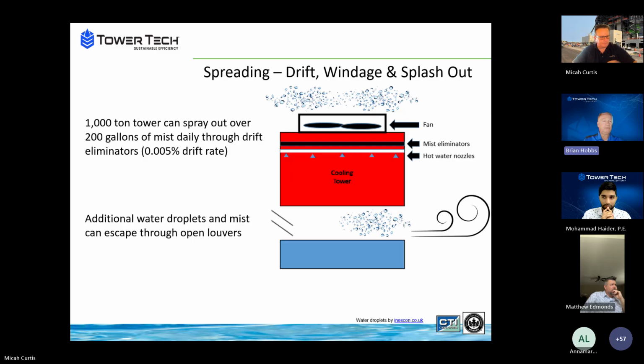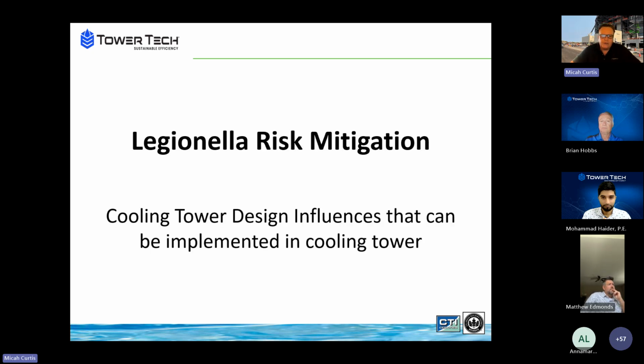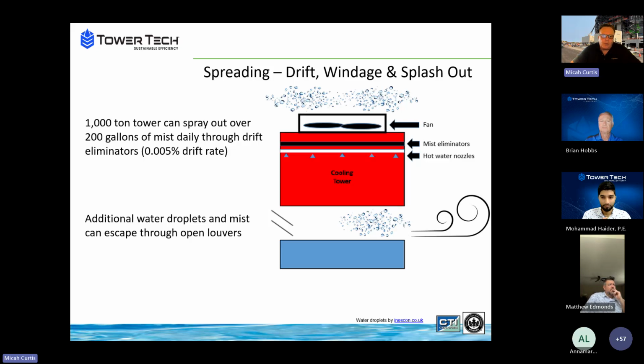Okay, so on a nominal 1,000-ton tower, 3,000 gallons a minute, over the course of a day, you're going to lose 200 to 216 gallons at a 0.005% drift rate, which is an ASHRAE standard for conventional cross flow induced draft cooling towers. So a lot of water droplets coming out of the top, as well if the wind is blowing in the right direction, will get some droplets picked up and blown out through the louvers in some cases as well. So that's a lot of water, 200 gallons a day. So a 1,000-ton tower can emit 200 gallons a day. More than people think, because the point here is 0.005% is a small number compared to the actual cooling tower evaporation that would occur, probably between 1 and 2%, depending on the delta T the system's designed for to evaporate.